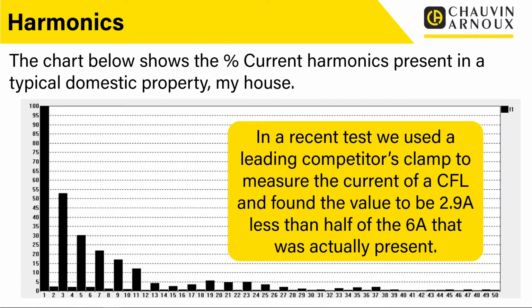But using a standard, and this wasn't a cheap clamp meter. This is a good quality clamp meter from a good manufacturer. It was measuring less than half what was actually present because it just wasn't designed for the full frequency response. So you do need to be very careful, if you're measuring currents, that you are actually taking into account the full frequency response. So you can see here, does this actually apply to the type of installations I work on?